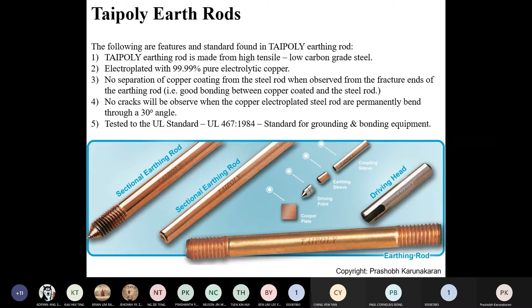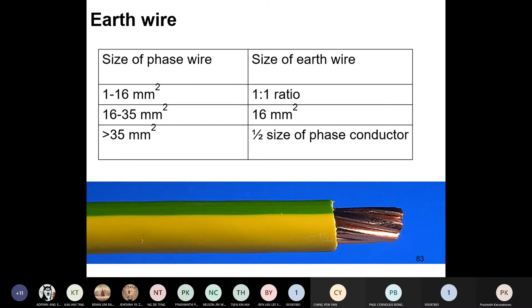Okay, so for the earth rod, this is the spec. What goes into the ground, the wire size going into the ground, must follow the incoming size. If your line is 1 to 16, it's 1 to 1, that means 16 must go to the ground. So in this case it's 25, if 25 is coming in, 16 can go to the ground. But if greater than 35 mm square, half the size of the phase conductor. This is an IEE standard, actually now it's IET, right?